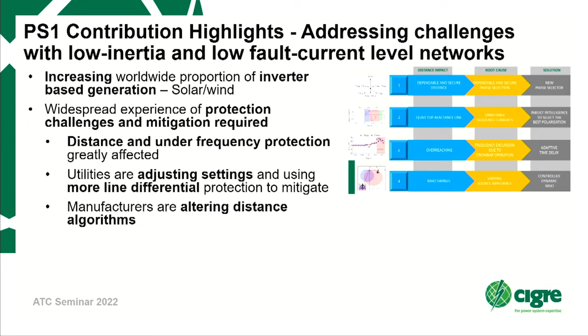Depending on the location in the network and the degree of inverter-based penetration, more time-consuming electromagnetic transient-based short circuit analysis studies may be required to correctly set reliable protection systems.